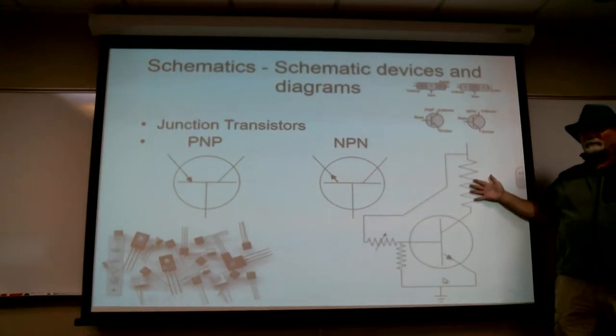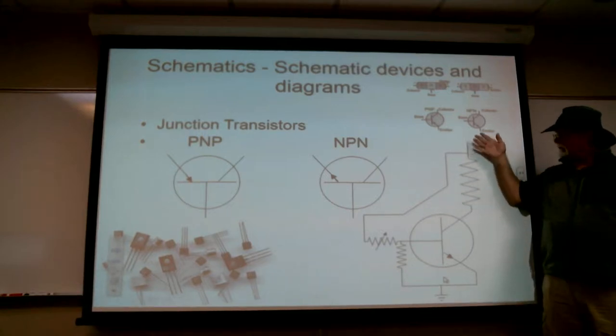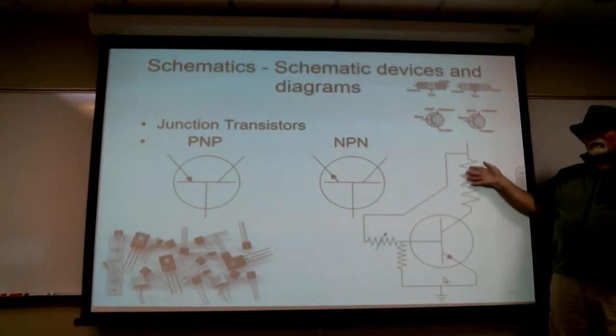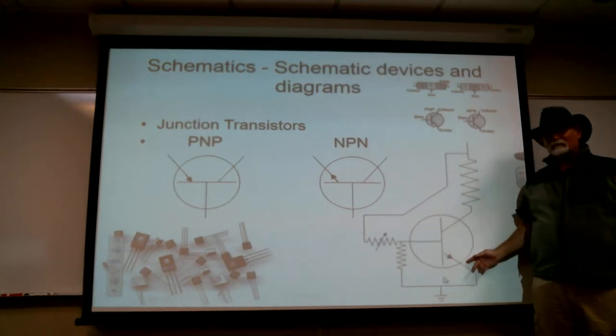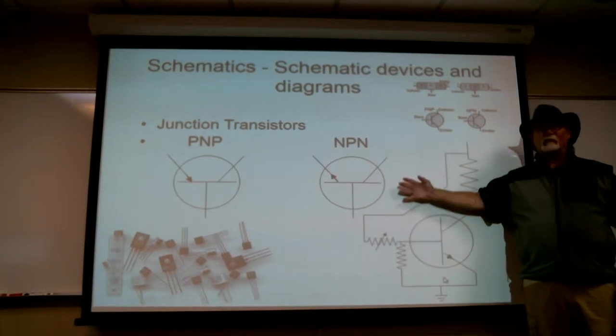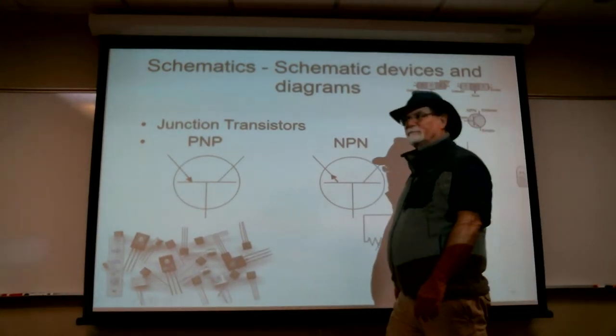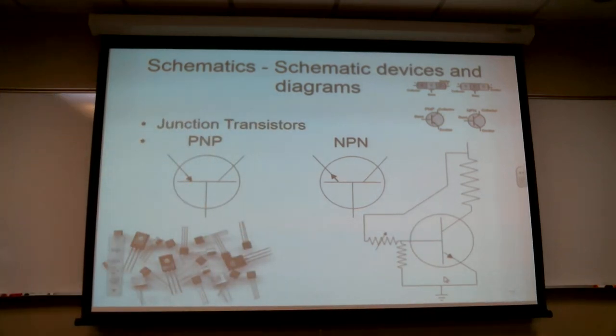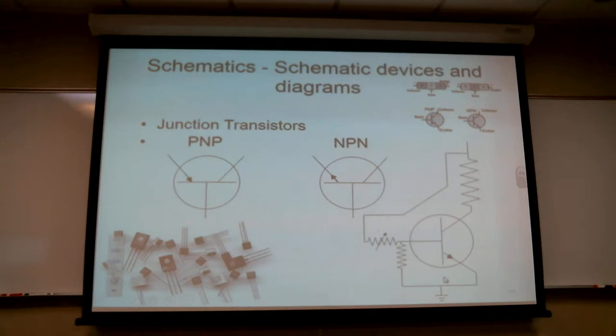Almost always diagnostically, either power is bad, ground is bad, something's wrong with the load or the wires in between. If the output transistor has failed, or any of the magic behind it has failed, you're going to replace it all. From experience, I have yet to find a blown-out output transistor that just magically blew out on its own. Every single time — and it's been hundreds — the reason the output transistor fails is because there's something wrong with the rest of the circuit.